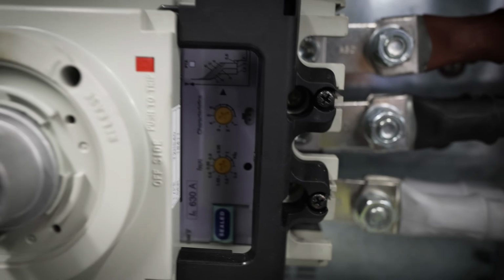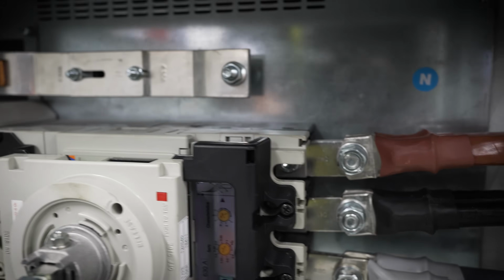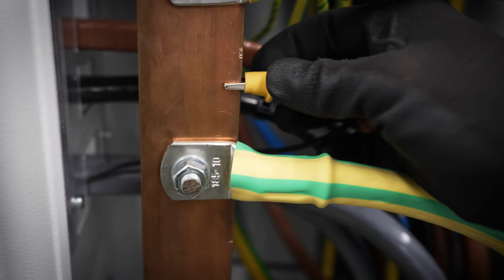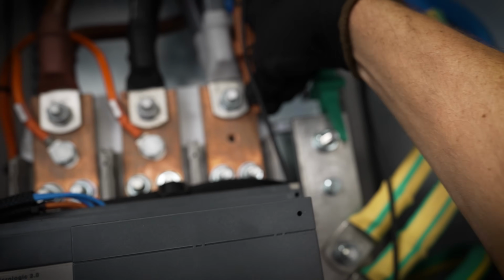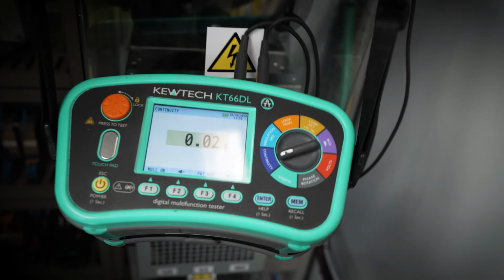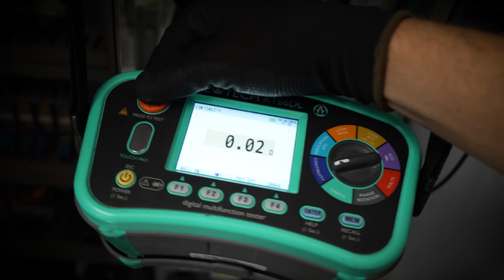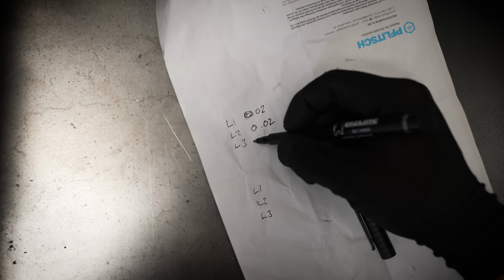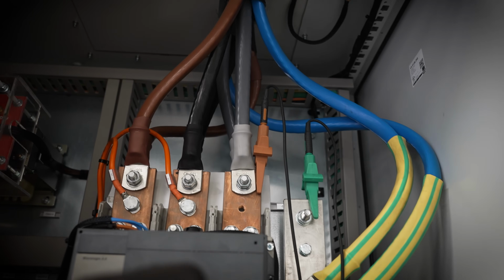All right, back in here. I'm going to try and get this on L3, but I think I'm going to have to move it. I could get that in the middle. That'd be nice, middle of the two. There we go. Sweet. Then here we want to get this on L3. And we can press test. 0.02. Lovely, as expected, and nice and low. Excuse my handwriting, ladies and gentlemen. I'm basically illiterate. So now we're going to do insulation resistance tests between Earth and all phases, etc.